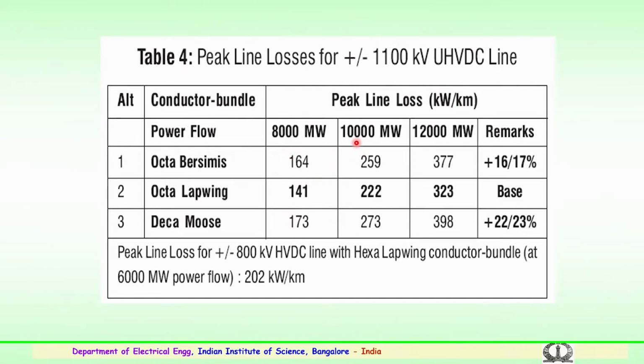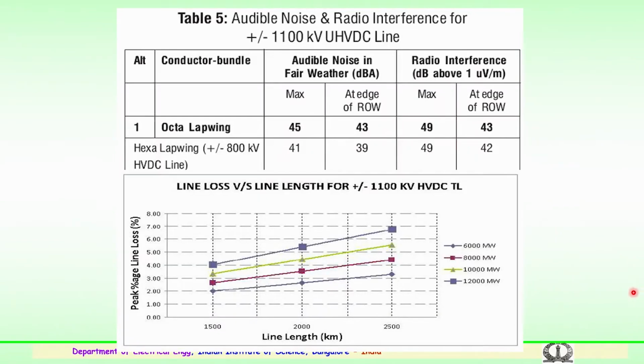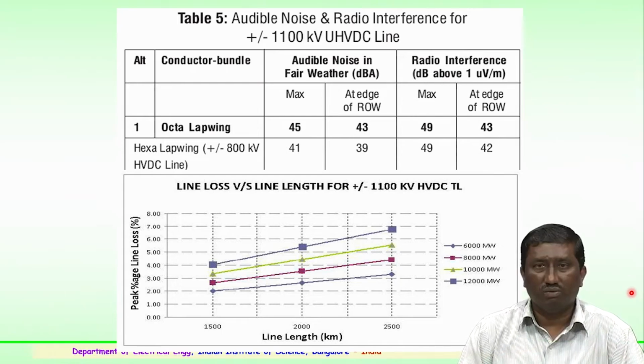In case the power transmitted is 10,000 megawatts, then the loss will be 259, 222 and 273 respectively, kilowatt per kilometer, for the 3 different conductors. And if the transmission system is transmitting power of 12,000 megawatts, the loss in kilowatt per kilometer will be 377, 323 for the lapwing 8 conductor bundle, and 398 in case we use the 10 conductor bundle of Moose conductor. So, this is how the peak line loss estimation is done for various power flow conditions. Similarly, audible noise and radio interference limits have also been estimated for 1100 kV.